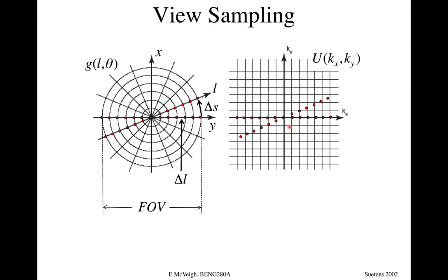And the delta kx here gives us the dimensions of the field of view, or the replicants of the image, right? So in order to adequately interpolate onto this grid, you have to have a reasonable distance between these points, right? And so out here, for example, if I needed these two values, the closest values I have, if the other angles down here are pretty far away, right? And so I'm going to have to do a lot of lengthy interpolation and smoothing to figure out what the data is in here, and I'm undersampled out here. And so that's going to give me artifacts.